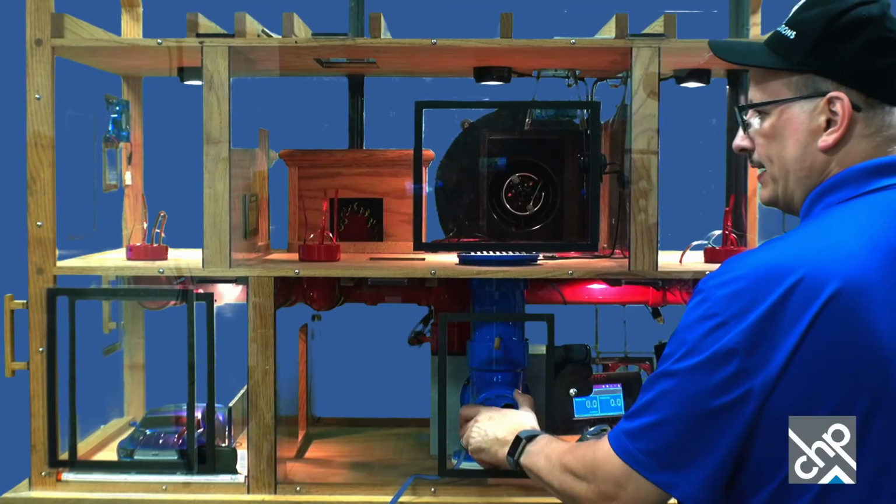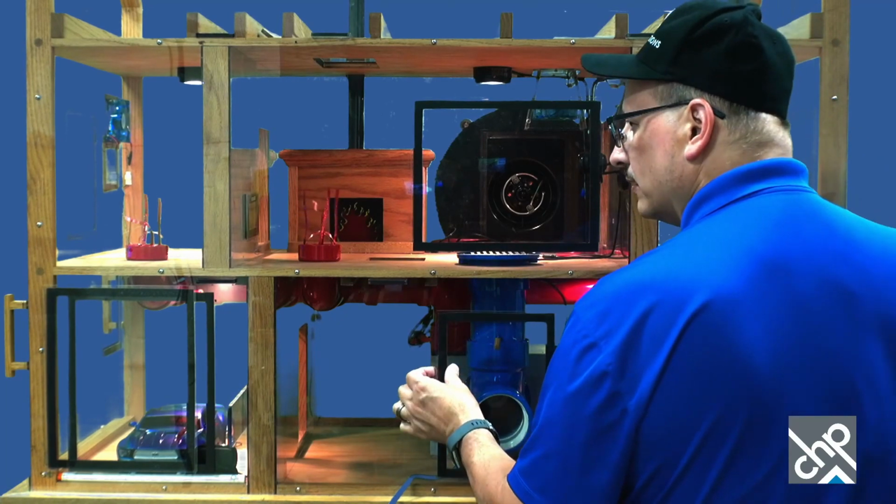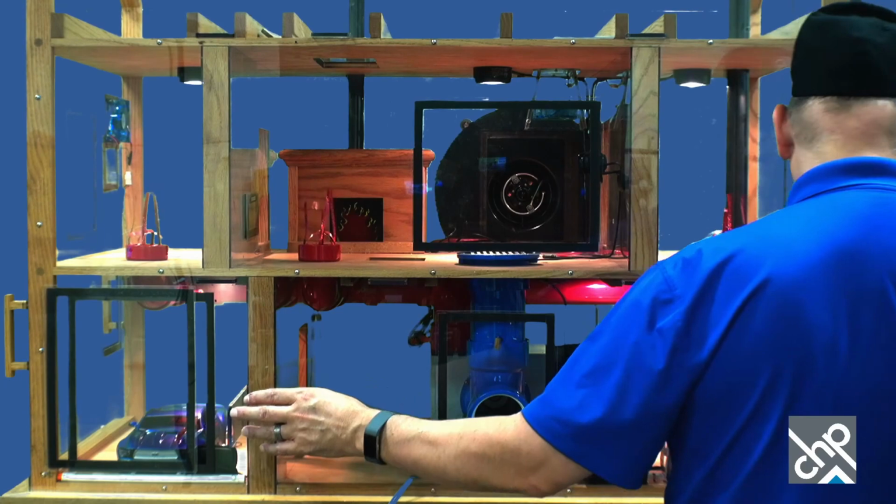So let me close this. You kind of see how it's stagnant there behind the car, and then when I open it up, you can see it get pulled in toward the house. And if I go back out here and take this leak completely off, let's see what happens. So if I, let's go back to the basement view, or garage. Closed.